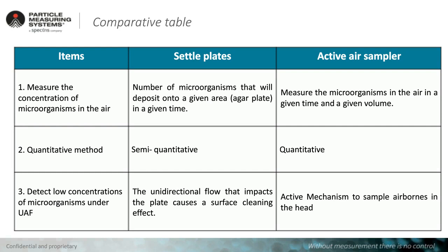Settle plates, unfortunately, just give us the number of microorganisms that will deposit on a given area. That means it is a measure of surface cleanliness and not a measure of air cleanliness. By that meaning, the settle plates are not really giving quantitative but only semi-quantitative results, because you cannot give a real reference, only a reference volume and a reference surface. In active air samples, you can give that per volume and time. That's why it is a clear quantitative method.